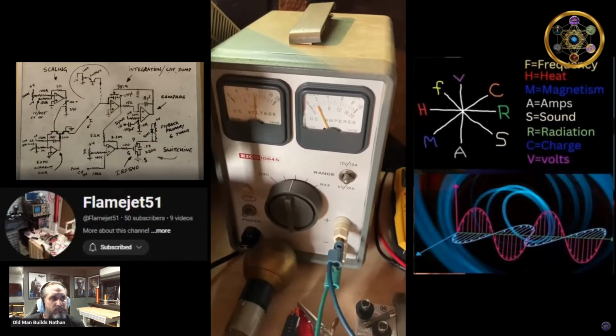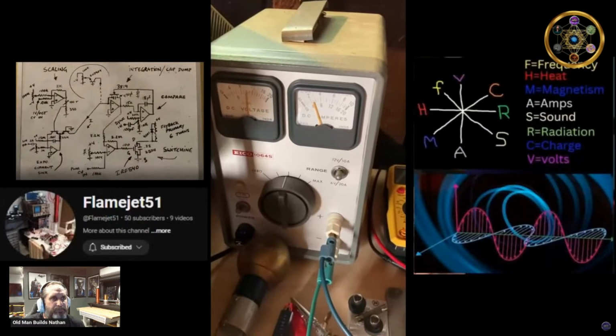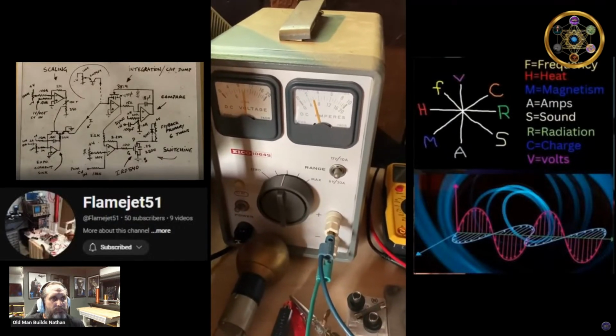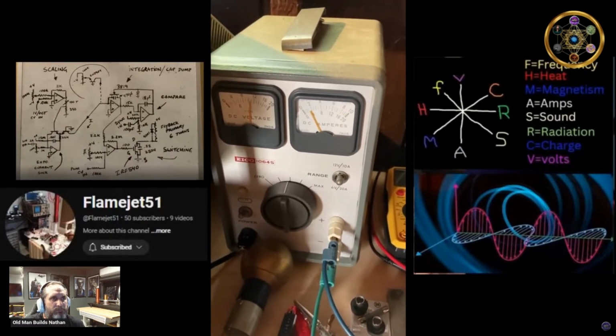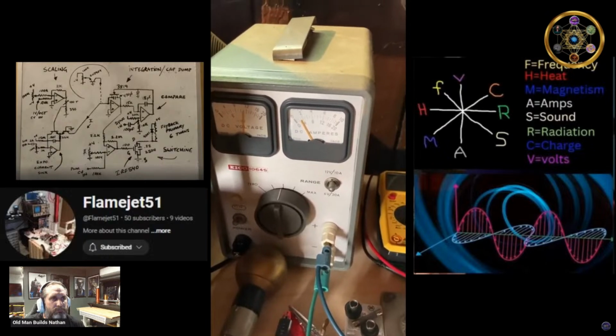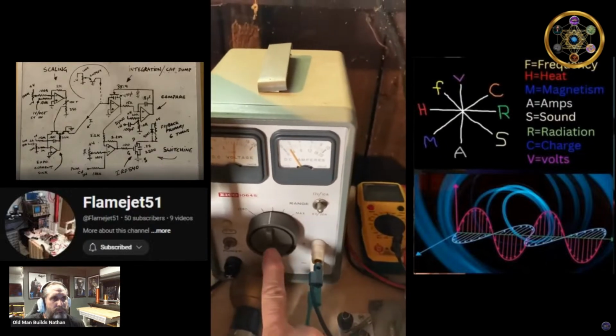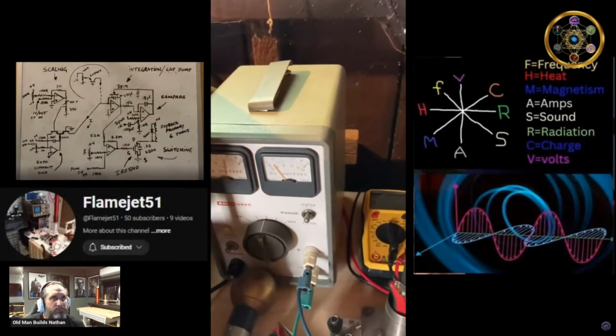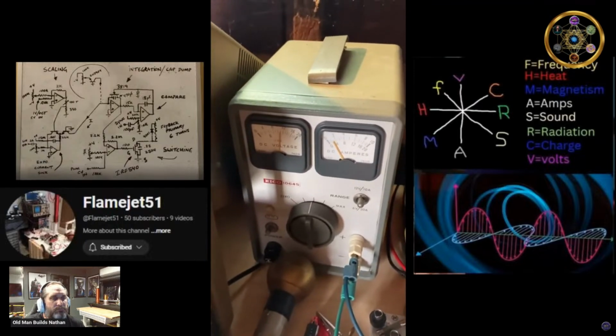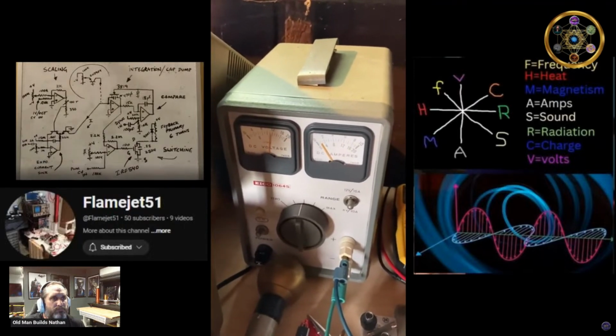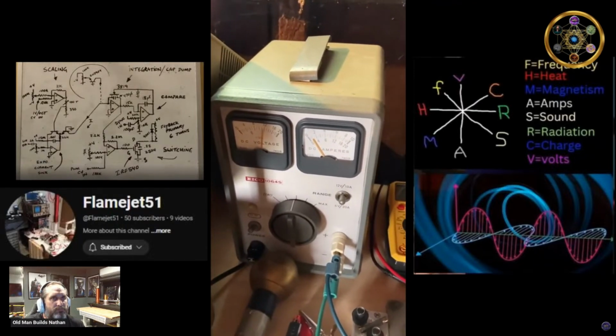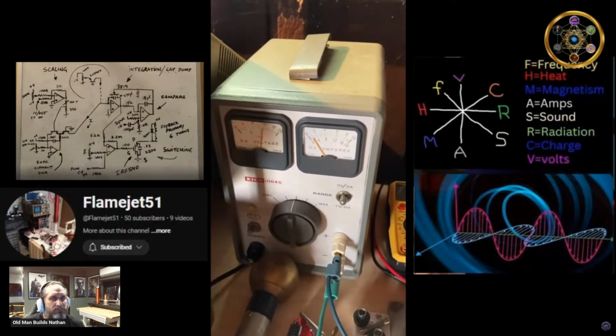All right, we'll go the other way. Notice the amps are rising, voltage is dropping, right? There's your duty cycle action. I haven't adjusted the voltage at all, okay? Now when we look at the frequency, what happens this time, right? As I go up in frequency, the amperage drawn goes down, right?